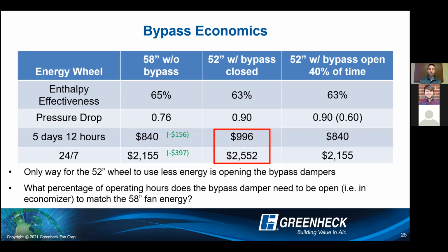So it's likely not going to be half of the pressure drop. But in this situation, that's what we looked at. But you can see 40% of the time, and generally, especially in the Southeast, you're not in economizer 40% of the time. So maybe certain applications, maybe on the West Coast, it makes sense if you have a lot more hours worth of economizer.